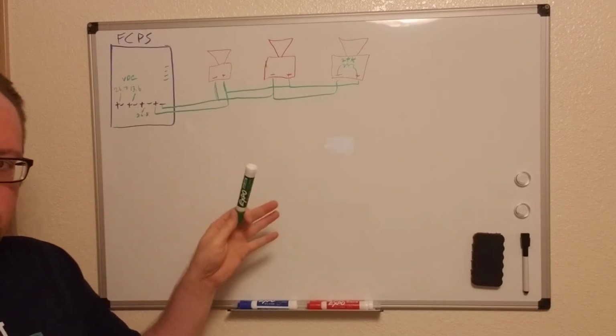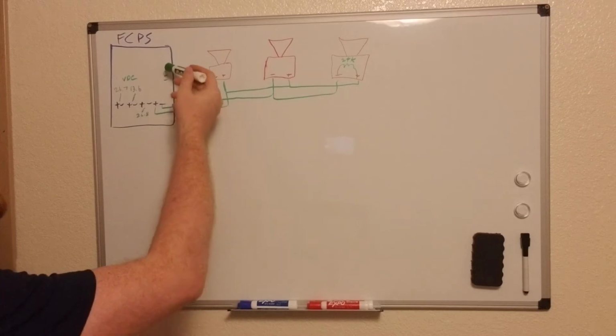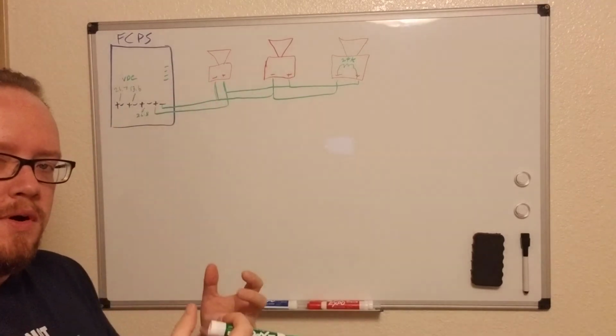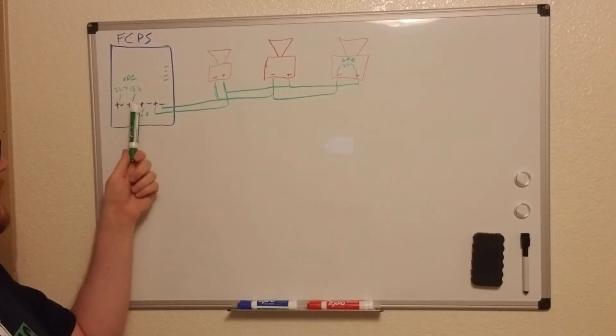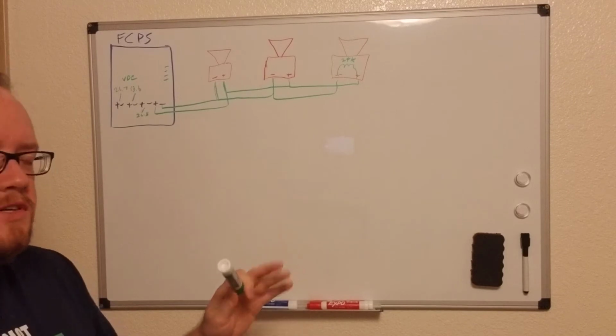First thing you're going to do when you walk up to a power supply that's got an output trouble, you're going to put your meter right there on the output from that board, and you're going to check and see what the voltage is. First thing you do is always, what is the voltage?